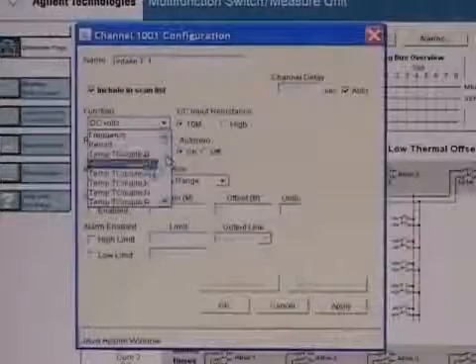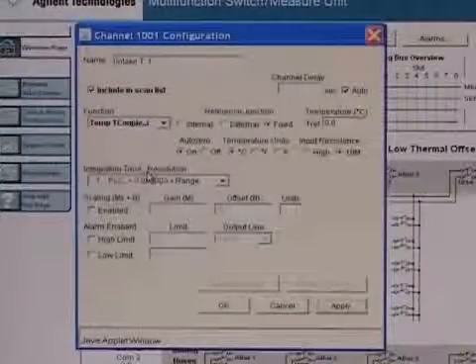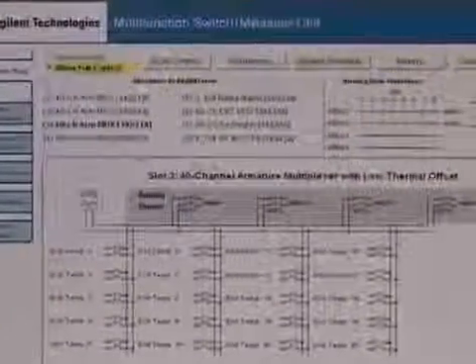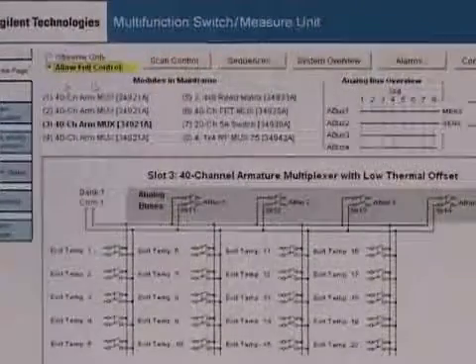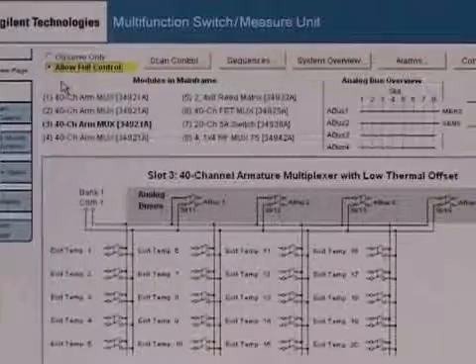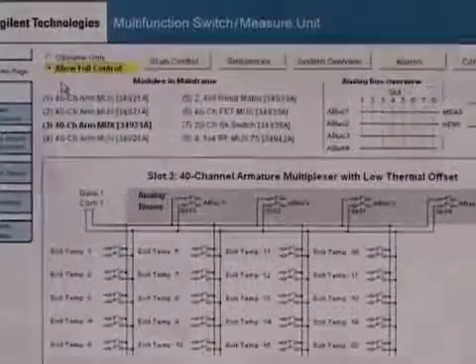Each 34921A multiplexer module supports up to 40 channels with your choice of thermocouple, thermistor, or RTD transducers. Eight modules may be installed in a single 34980A for up to 320 measurement points.